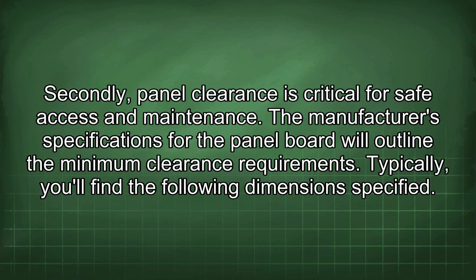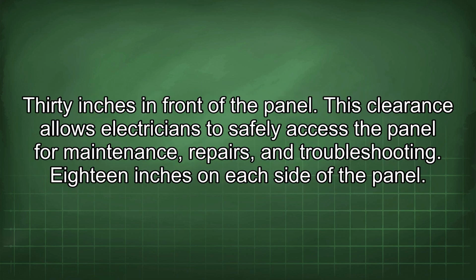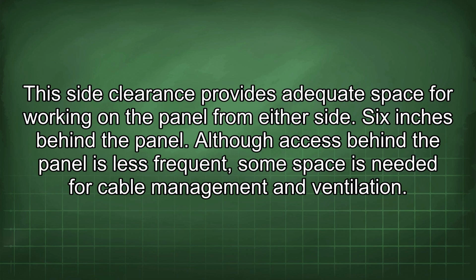Secondly, panel clearance is critical for safe access and maintenance. The manufacturer's specifications for the panel board will outline the minimum clearance requirements. Typically, you'll find the following dimensions specified: 30 inches in front of the panel. This clearance allows electricians to safely access the panel for maintenance, repairs, and troubleshooting. 18 inches on each side of the panel. This side clearance provides adequate space for working on the panel from either side. 6 inches behind the panel. Although access behind the panel is less frequent, some space is needed for cable management and ventilation.